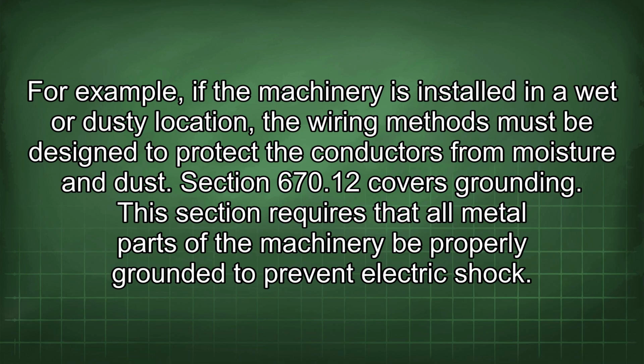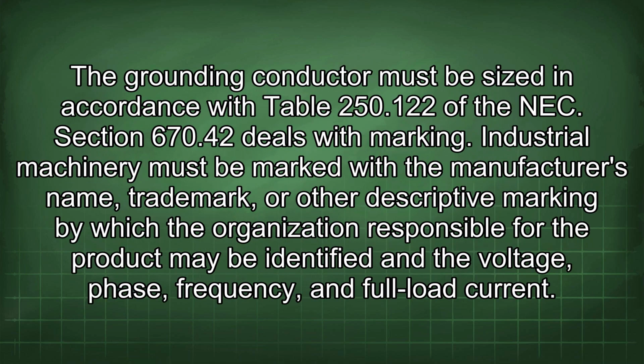Section 670.12 covers grounding. This section requires that all metal parts of the machinery be properly grounded to prevent electric shock. The grounding conductor must be sized in accordance with Table 250.122 of the NEC. Section 670.42 deals with marking. Industrial machinery must be marked with the manufacturer's name, trademark, or other descriptive marking by which the organization responsible for the product may be identified and the voltage, phase, frequency, and full load current.